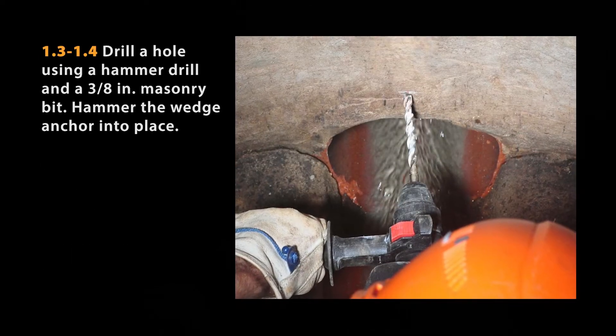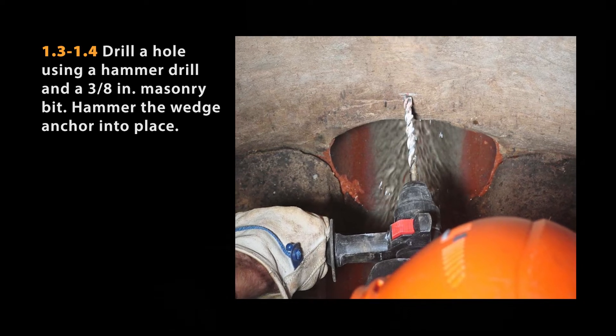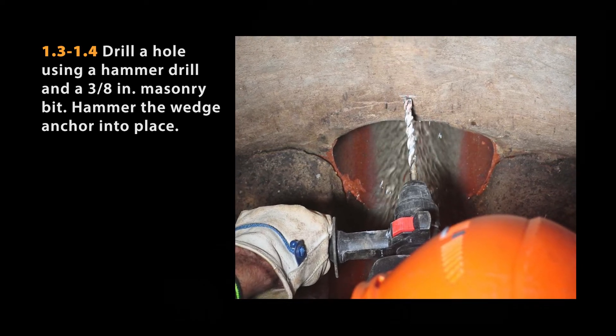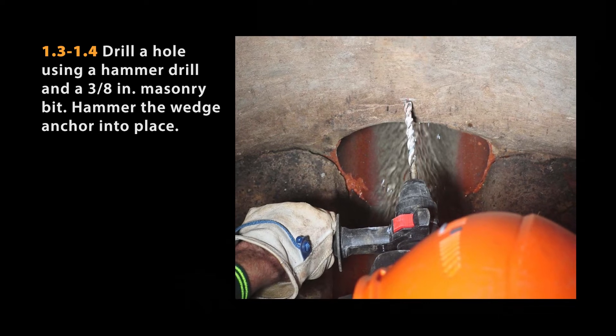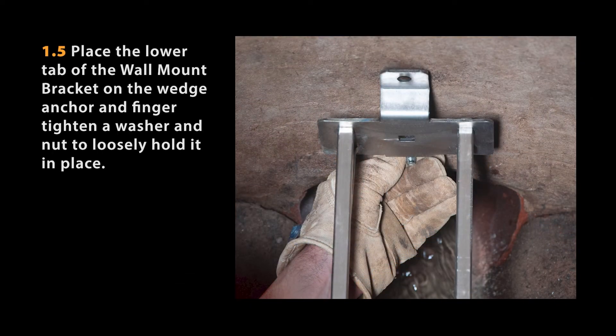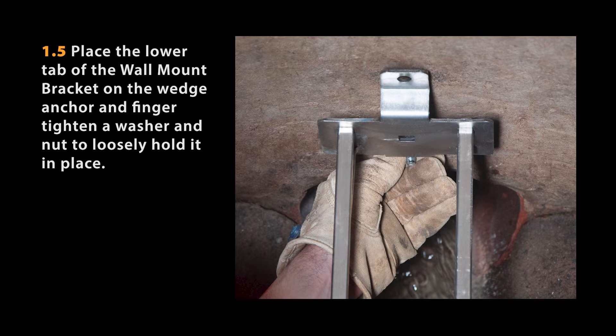Using the hammer drill and a 3/8 inch masonry bit, drill a hole at the marked spot. Hammer the wedge anchor into place. Place the lower tab of the wall mount bracket on the wedge anchor and place a washer and nut on the anchor and finger tighten.